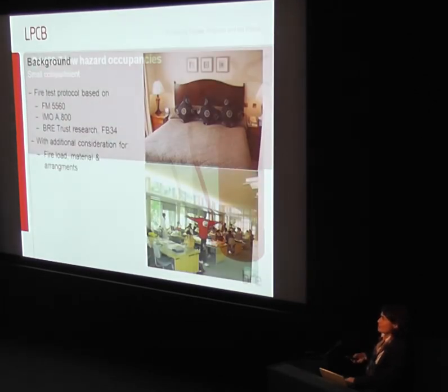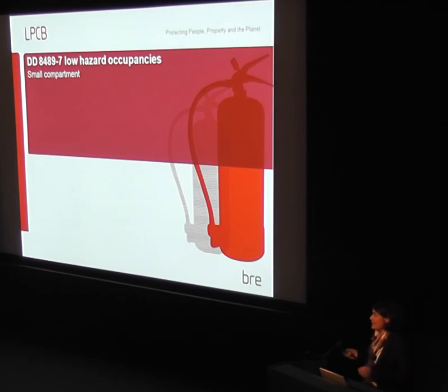Some consideration has been made to Europeanise the standard arrangements, and also to take account of the fact that a lot of the standard tests done by others are 10-minute tests, but the real application would be sort of half-hour type applications. So some of the post-analysis of the results, in terms of whether the temperature is being controlled, is assessed, not just a single temperature as the pass-fail criteria.